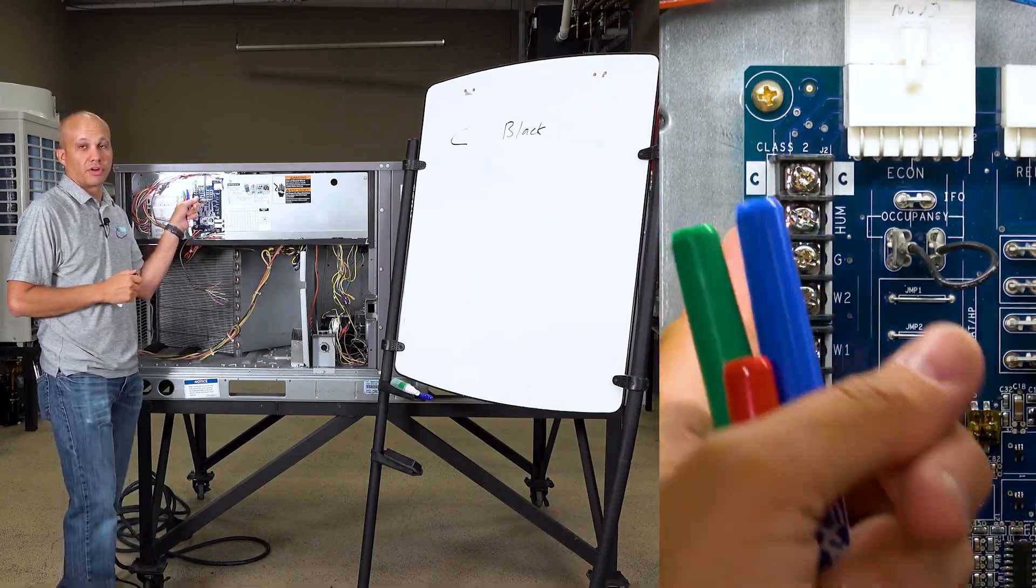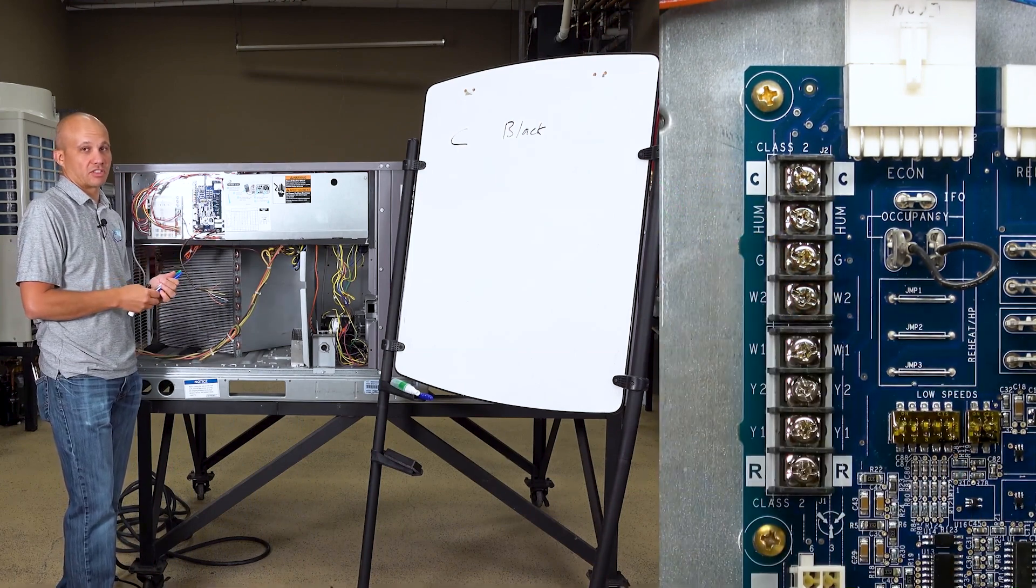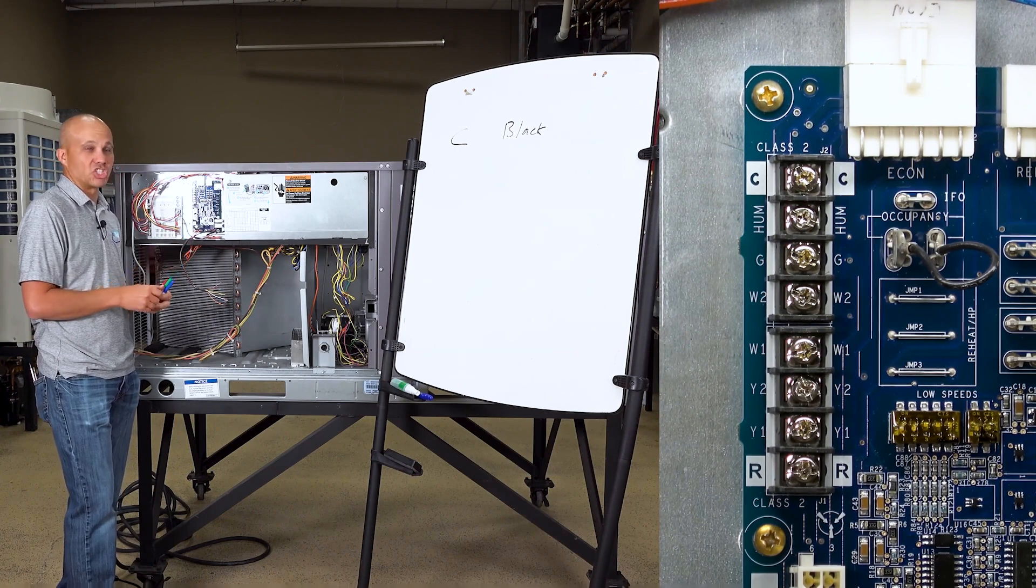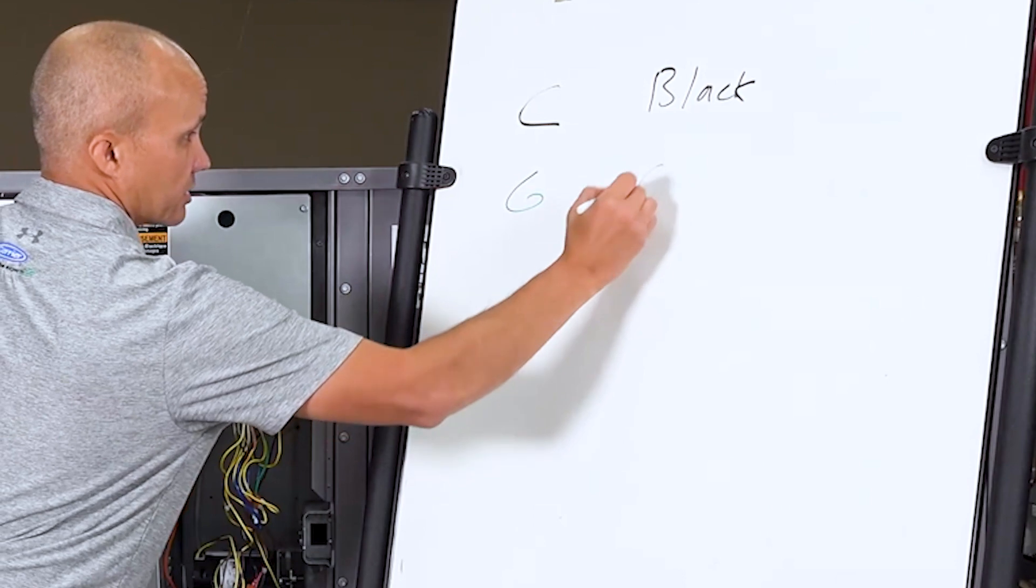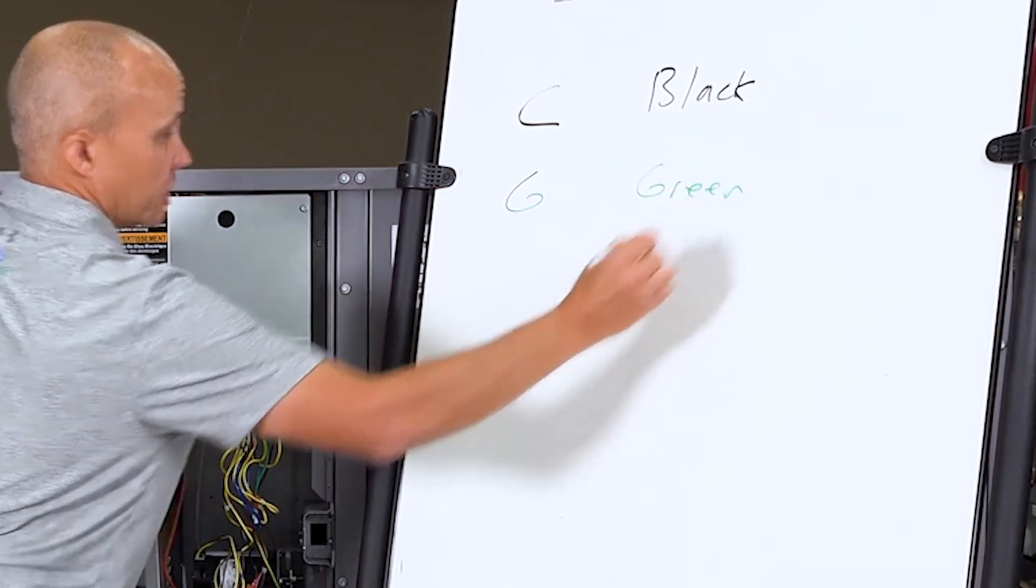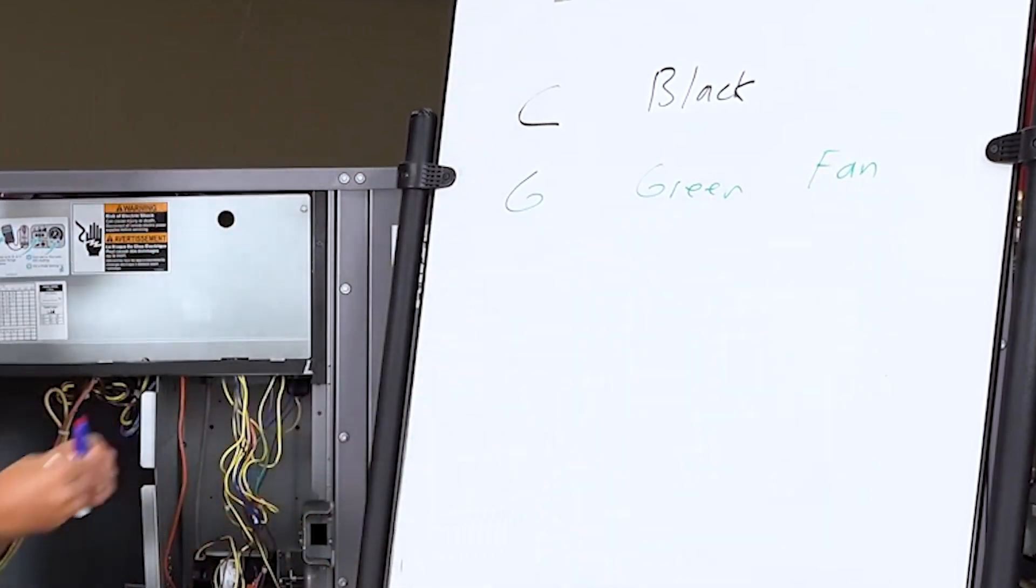The next one on here is a hum terminal for dehumidification. We're not using that in this application, that's not a standard thing, so we don't need that. The next one is G. G is going to be green, that's why it's called G, and G is going to be for our fan. G is always fan. I should also probably say in this case the C is going to be common, we'll keep it consistent on the board there.